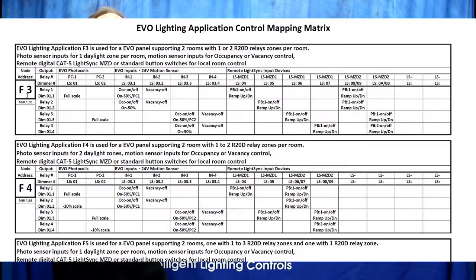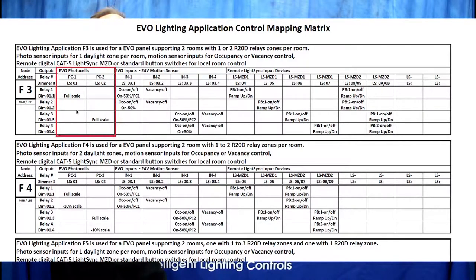Let's review lighting application 3. In this application we are using both photo sensor inputs for daylight harvesting. The first photo sensor input controls dimmer 1 as the daylighting zone in the first room, and the second photo sensor input controls dimmer 3 as the daylighting zone in the second room.